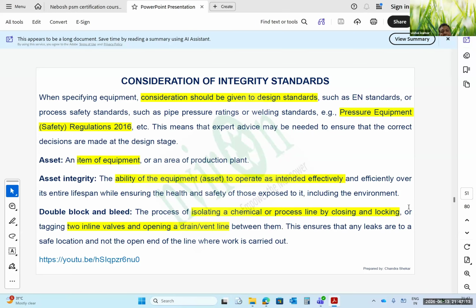So when doing any maintenance work, we have to give the PTW, the permit to work, and isolate both the inlet valves and both the outlet valves. Sometimes a blank is also fitted in the valves, so in any case if there is leakage, the person working in that area cannot be exposed to the hazardous chemical. We also drain the pipeline, vent it, and flush it so that no trace of chemical remains in the working area. That is called the double block and bleed system. Clear?